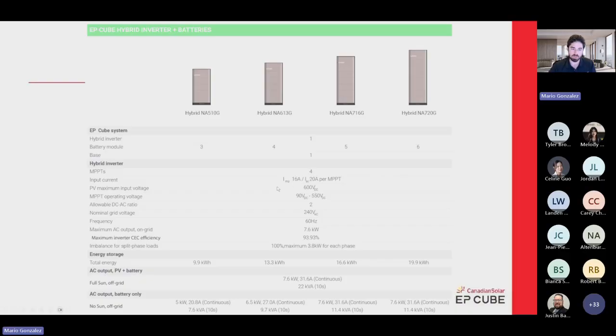The IMP for each MPPT is 16, with 20 amps short circuit. This is a 600 volt DC system. However, the MPPT range for the system is from 90 to 550 volts DC. Again, 550 volts is the top end. You want to account for temperature variabilities and how that affects your panel production, right? If temperature decreases, voltage increases. So you want to make sure you don't put too many or too few panels, because if you put too many panels, that's going to trip the circuit. It's going to turn off your solar production. The AC to DC ratio is 2.